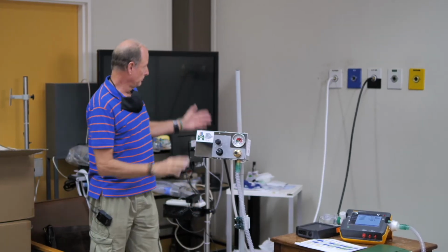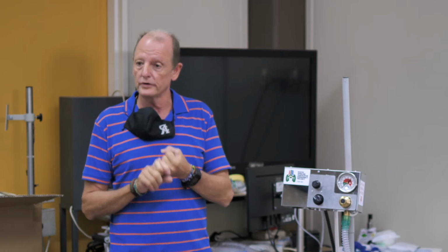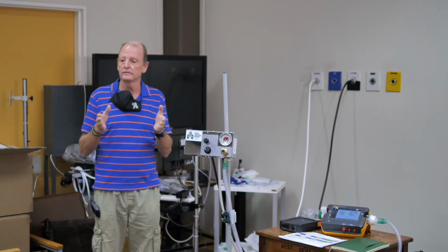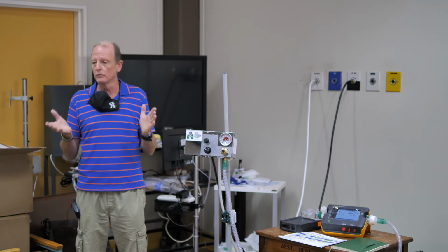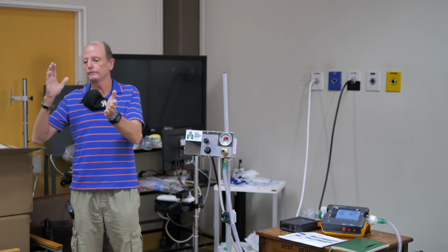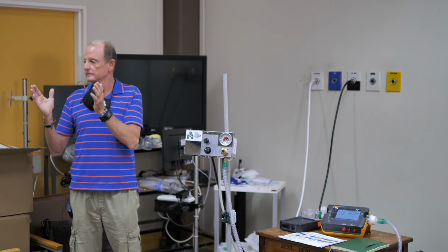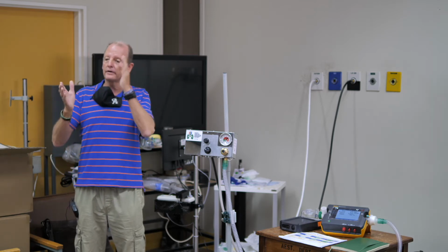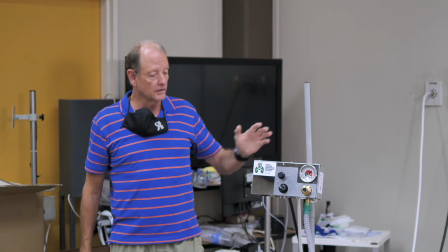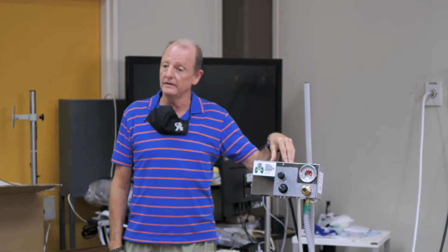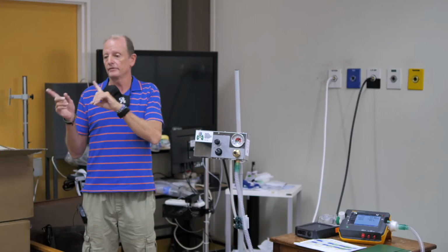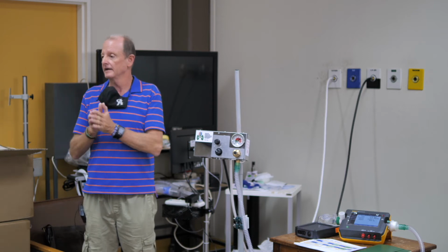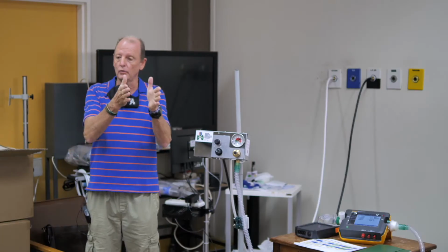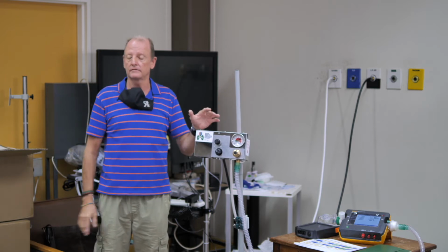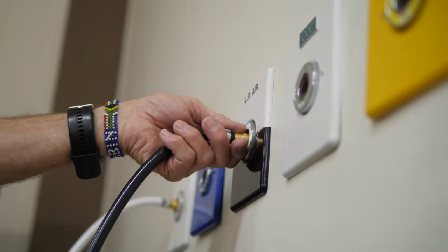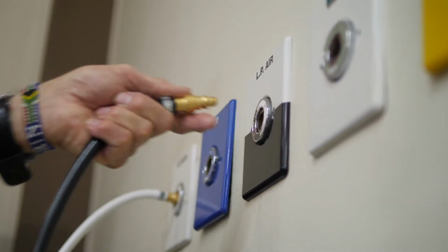With the unit, plug it in, check your wall pressures. Check that you have got sufficient wall pressure, which is normally in the region of 420 to 450 kPa. Okay? If you've got a big variance in your wall pressure, because this unit has got an oxygen blender in it, they have the differential of pressures, you'll get an alarm, a whistle. So check your wall pressures before you start saying, oh, there's a problem here. Firstly, you want to check those audible whistles.